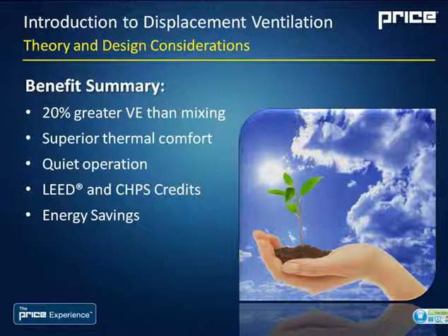So to summarize the benefits of displacement ventilation before I move on with the products, we see a 20% greater ventilation effectiveness than a mixed system, and that's translating to increased indoor air quality in the occupied zone. Again, we see superior thermal comfort simply because we're using warmer supply temperature and lower velocity systems. We're allowing the cool air to find the heat sources, and it's really thermodynamic dependent on how much cooling that body requires.